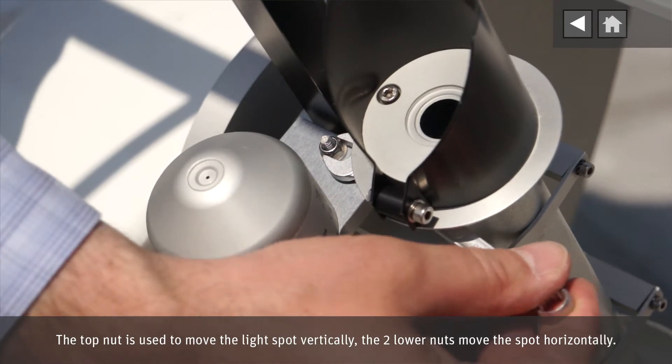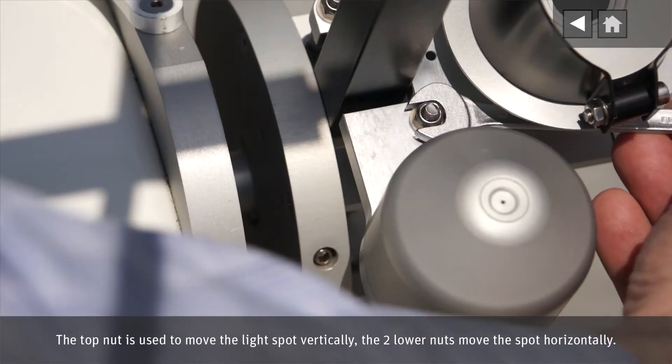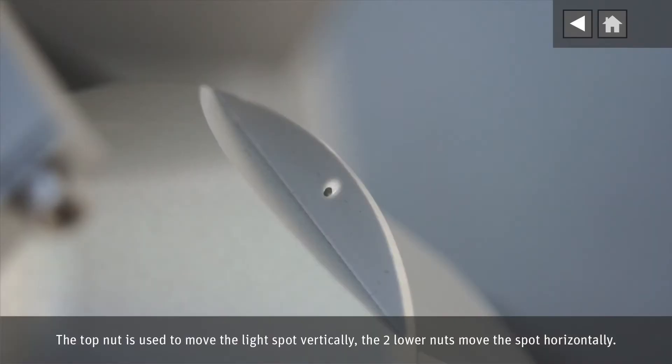The top nut is used to move the light spot vertically. The two lower nuts move the spot horizontally. Remember it takes 10 seconds for the SOLYS to respond to each adjustment.